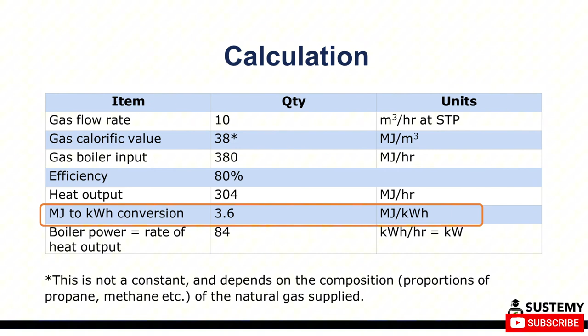That gives us a gas boiler input of 380 megajoules per hour, multiplying out those units. You can see the meters cubed cancels out when I multiply them. The efficiency is 80%. The heat output is therefore 380 times 80% equals 304 megajoules per hour, writing down the units. The megajoules to kilowatt hour conversion is 3.6 megajoules per kilowatt hour. So we divide the 304 megajoules per hour by 3.6 megajoules per kilowatt hour, which gives us an answer of 84 kilowatt hours per hour, or 84 kilowatts.